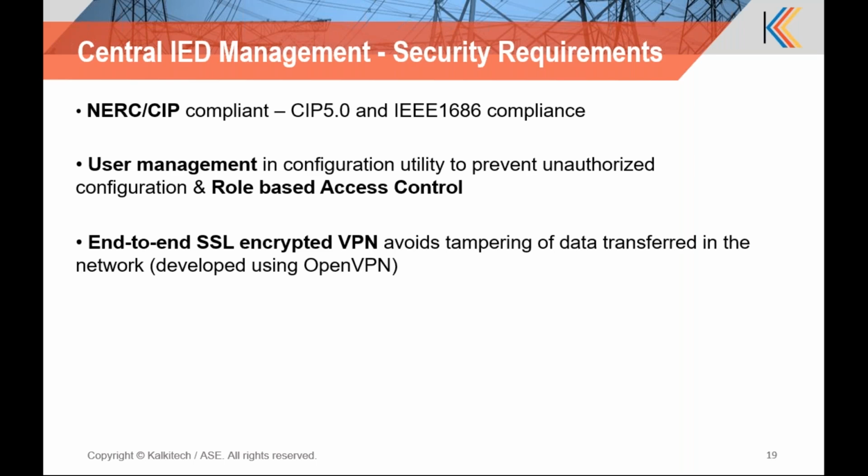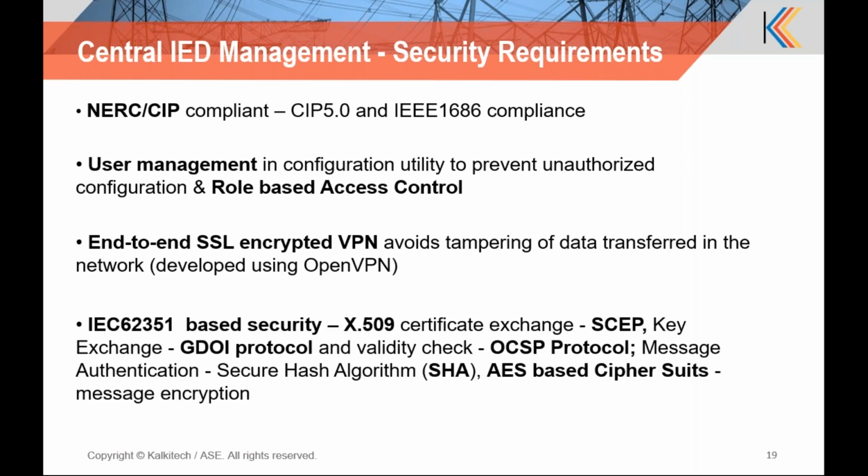Earlier we were using end-to-end VPN, but now they are changing to a TLS-based tunnel, and we support a TLS 1.2 based tunnel between the substation and the control center. Another key case is the 62351 based security standard. This is a detailed standard that has come up with security principles at various levels, like protocol encryption, and role-based control, where one person can only do commands, and another can view and command.